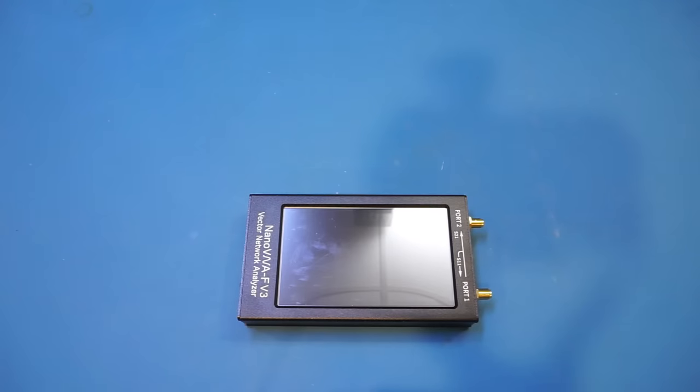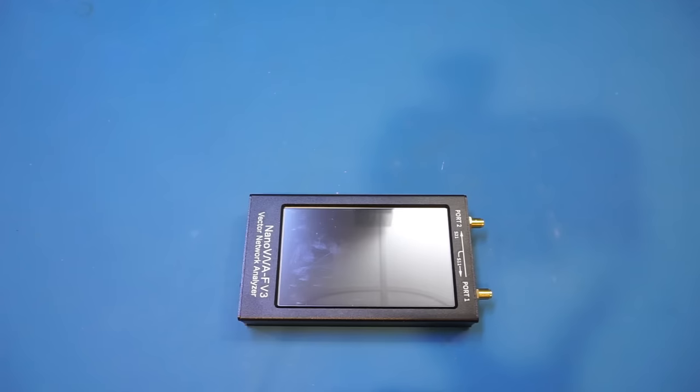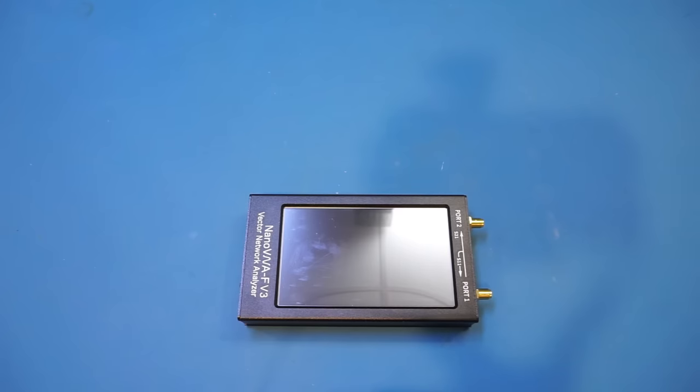Very briefly, most of my viewers probably are already familiar with spectrum analyzers, which can perform frequency and amplitude measurements. A network analyzer, on the other hand, can do amplitude and phase measurements, and can characterize both transmitted and reflected signals.